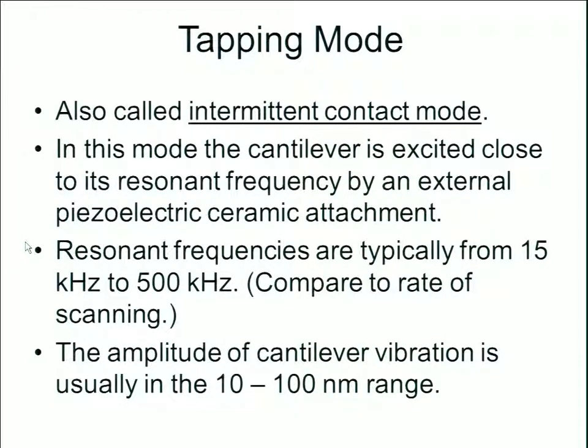Tapping mode, also called intermittent contact mode, can be thought of as a cross between contact and non-contact. In this mode, the cantilever is excited very close to its natural resonant frequency by an external piezoelectric attachment — a tiny piezoelectric mounted onto the cantilever that expands and contracts very quickly, causing cantilever vibration. Resonant frequencies typically range from 15 to 500 kHz.